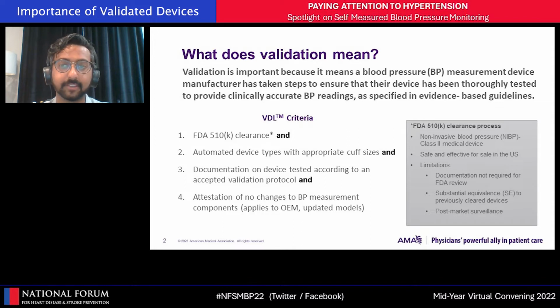It involves rigorously testing a device according to an internationally accepted validation testing protocol. Essentially, this is a clinical trial where devices need to show a low margin of error to pass, which does sound straightforward, right? Well, there are some challenges. Protocols get updated every few years. Requirements are revised. Some protocols may even get sunset. Only a few of these validation studies ever get published. And sometimes it's not clear if a device that went through the testing is the same one that's available on the market. Another huge issue is that devices should be validated with all cuff sizes that are available for sale, and that may not always be the case and may be hard, if not impossible, to confirm.